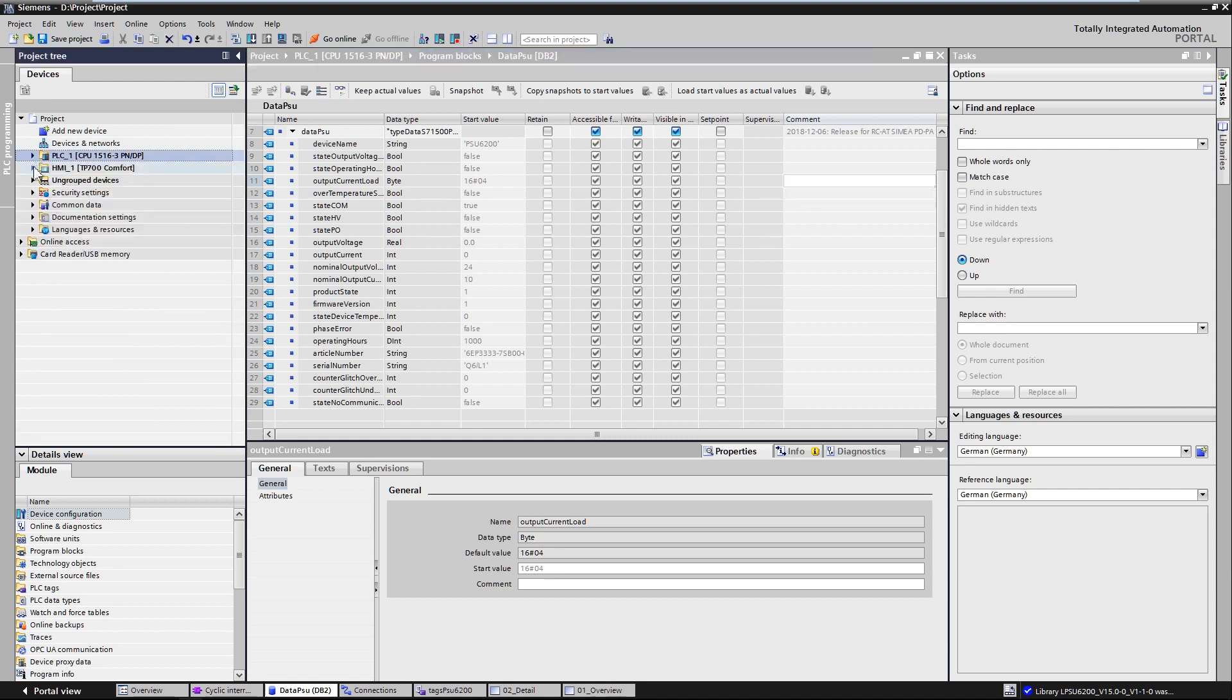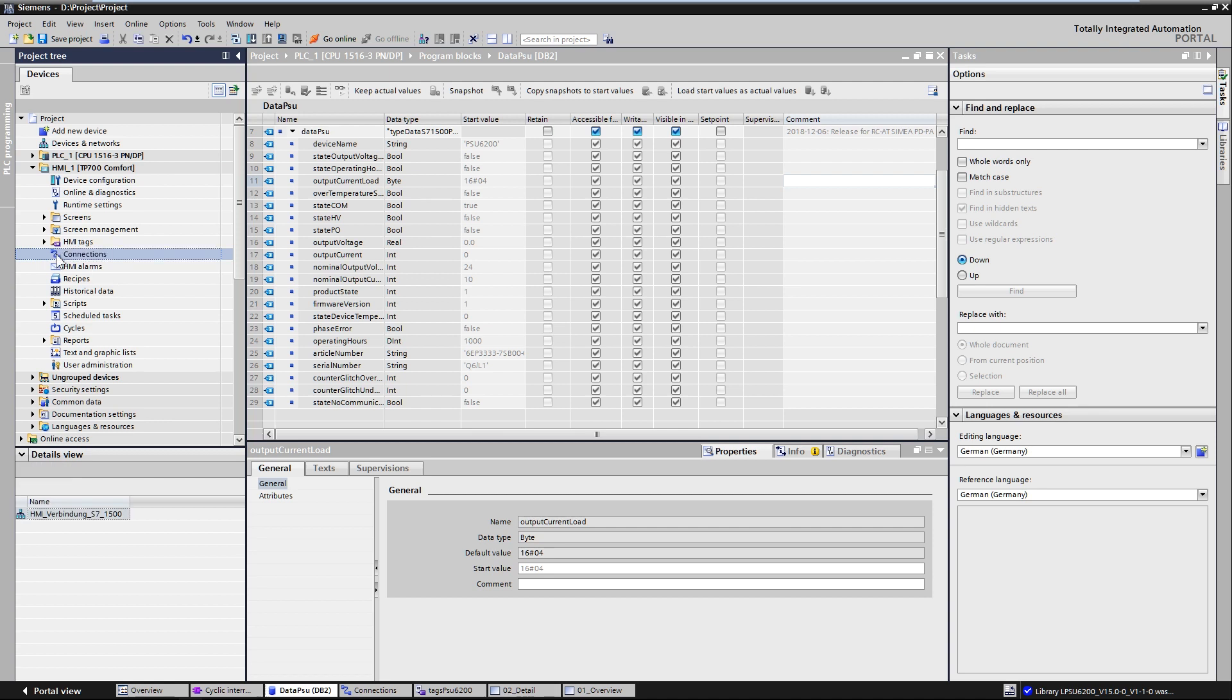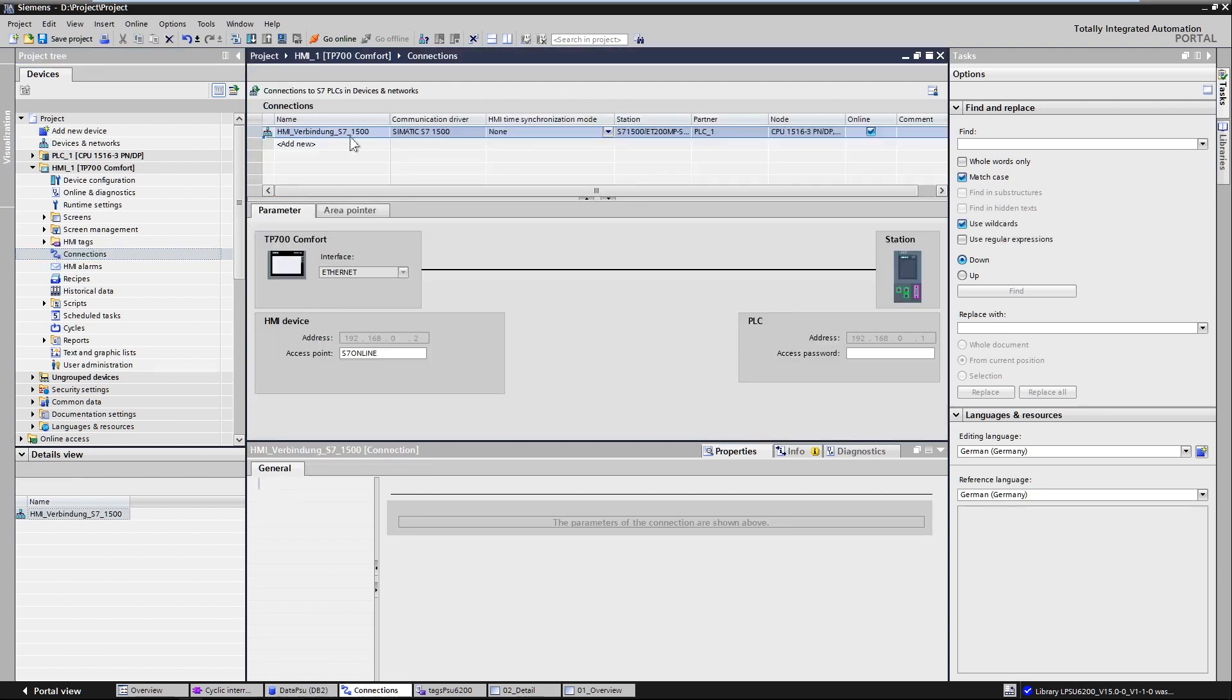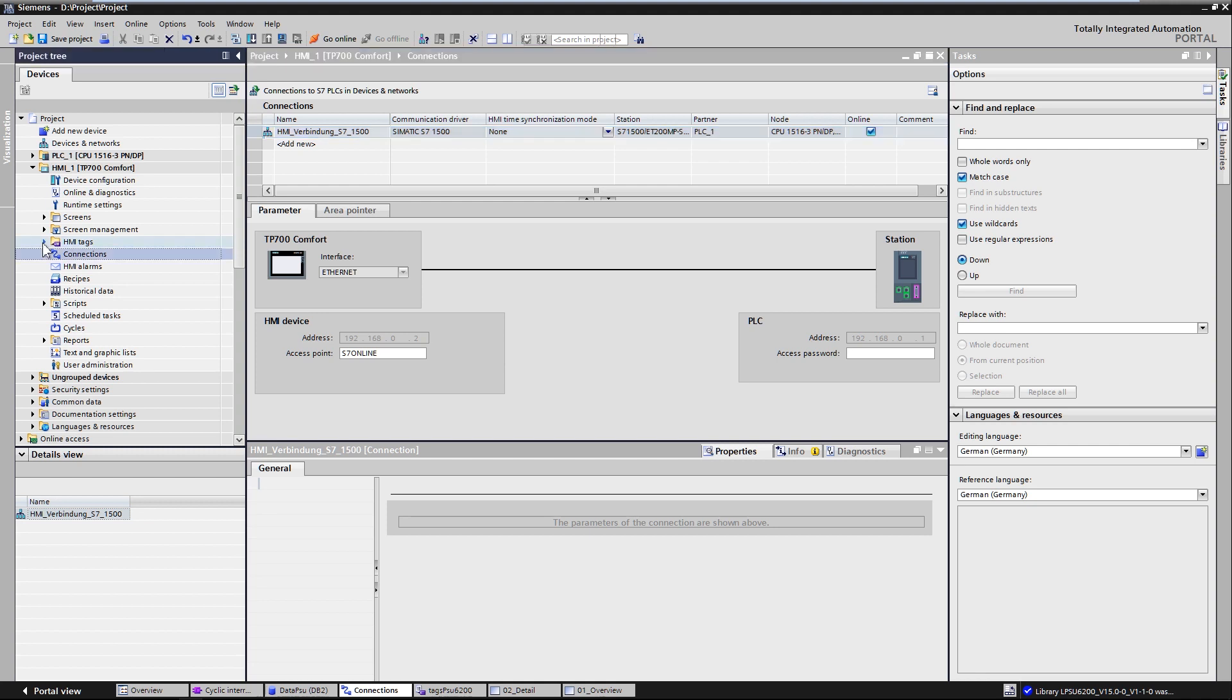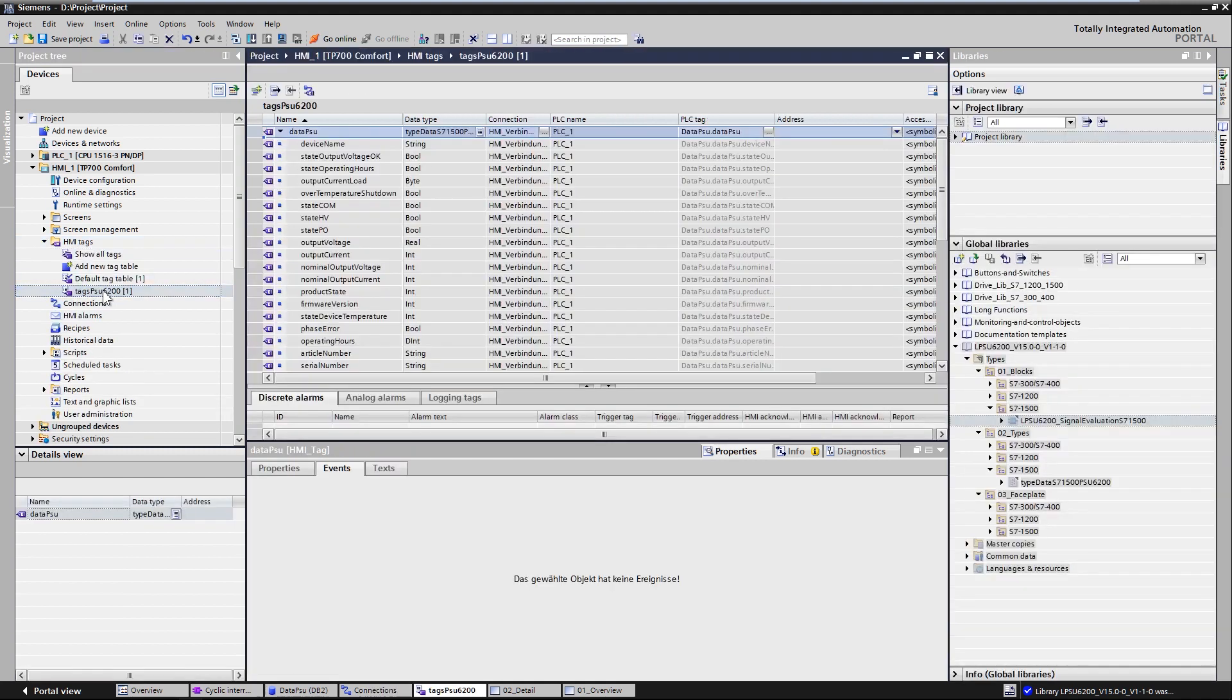To be able to use the picture blocks you will need an HMI connection from your operator interface to your controller. To connect the data to the screen block you need an HMI variable that references the associated PLC variable via the HMI connection.